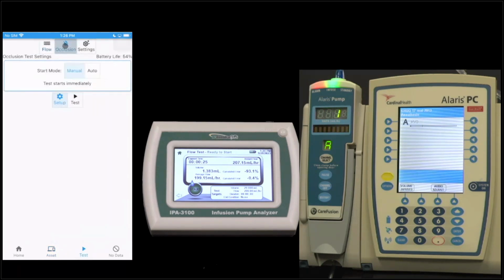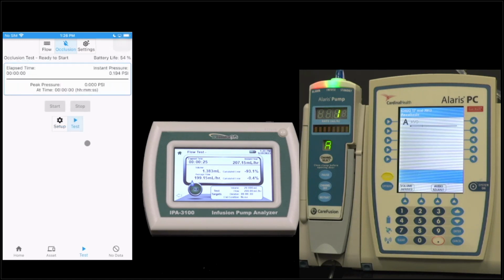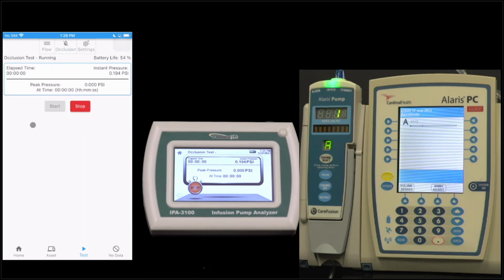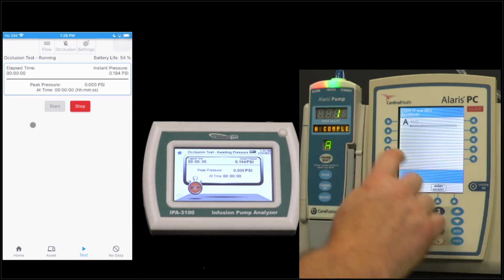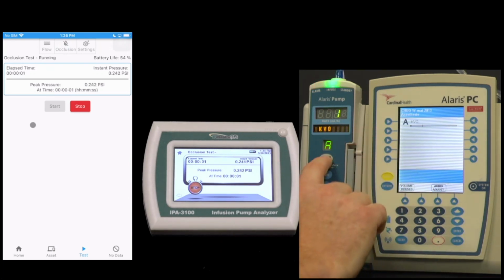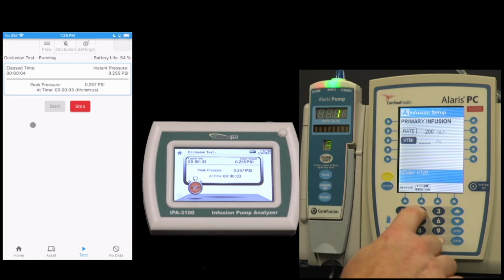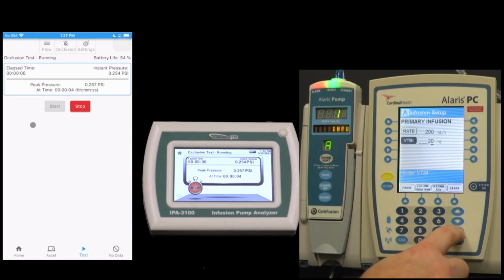So at the top, we can select occlusion. That's the test we want to run. Is it a manual mode or auto mode? I like the auto mode just because it automatically synchronizes. Now we can see the screen on the 3100 has changed to occlusion because that's the test that I told it I wanted to run. And we resume the pump. Oh, that's right, I've got to give it more volume. I only hit 2 milliliters instead of 20. So we'll go ahead and restart that.